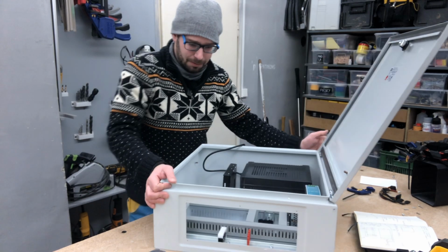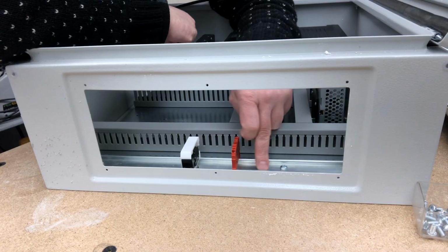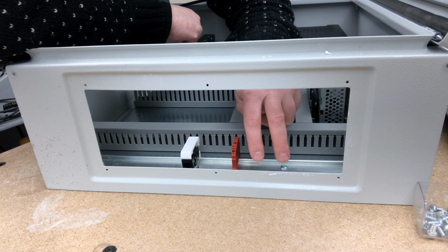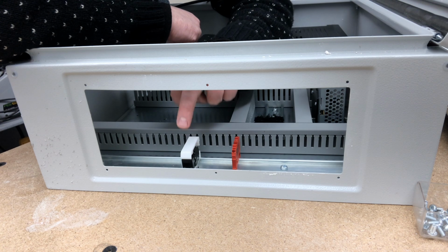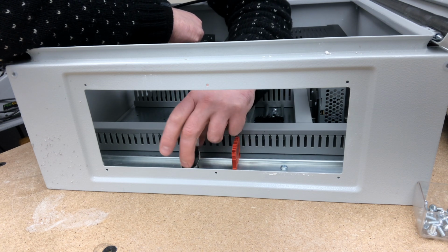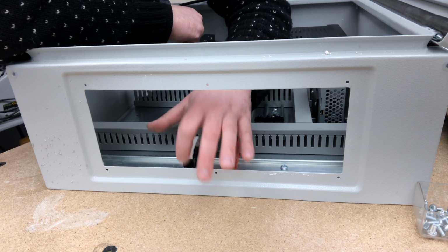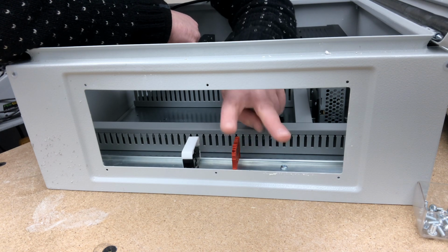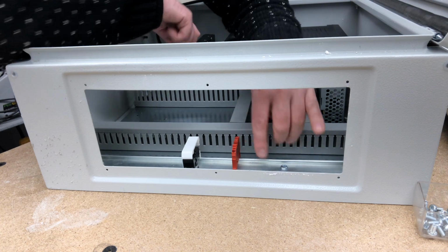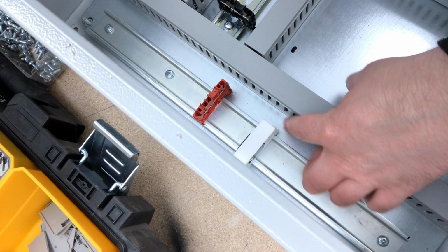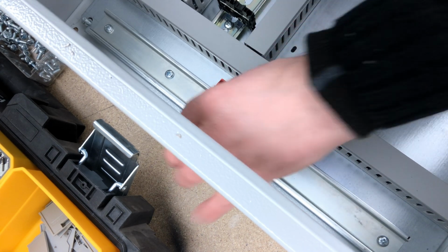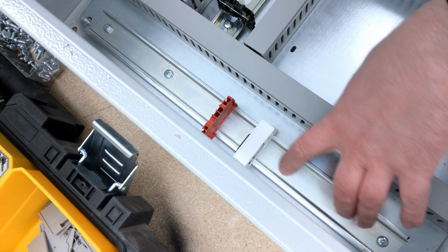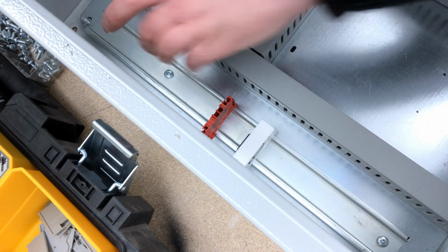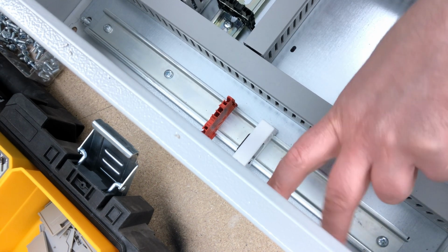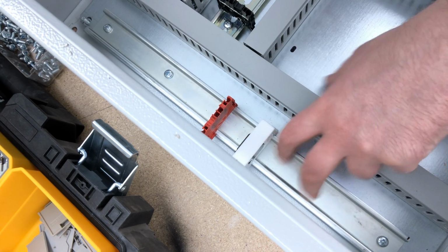It's like 3-4 millimeters from the cable channel, but that's okay. What is a bigger problem is this keystone. I put the DIN rail as close to the edge of the mounting plate as possible, but I forgot that this is quite low and quite tall, so I won't be able to put the cable in. Now I have two options and I think I have to combine them. I should be able to move the DIN rail like 10 millimeters to the back. I can mount this terminal upside down, and maybe I will be able to put this a little bit up, the whole DIN rail. So I will put some washers underneath just to help it a little bit, like 2, 3, 4 millimeters maybe, and it should help. Okay, let's do that.